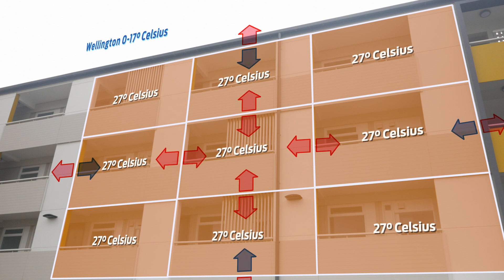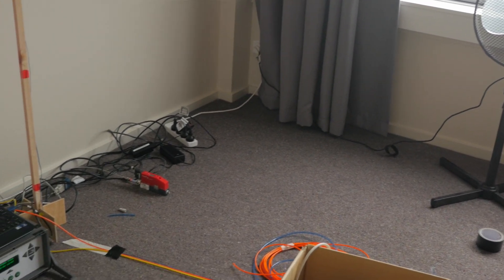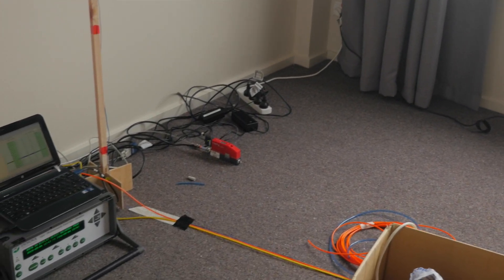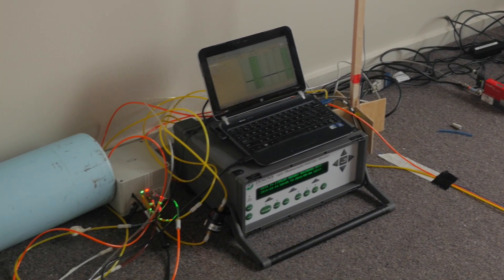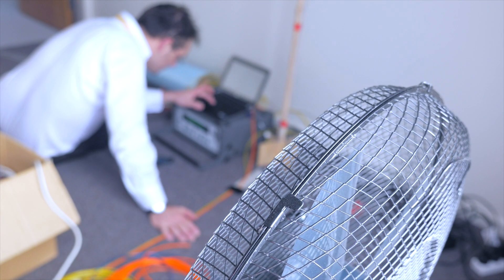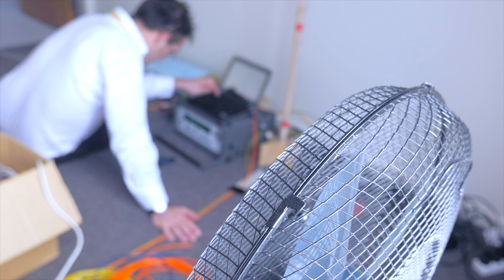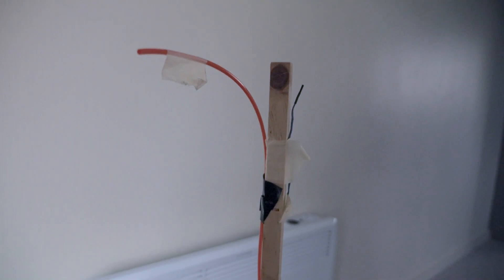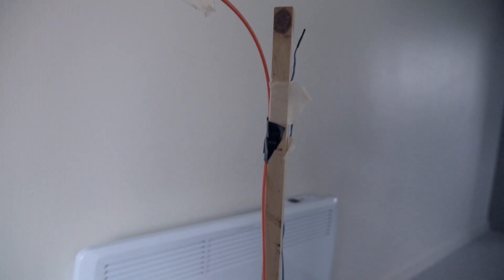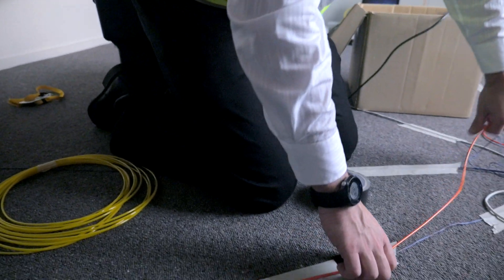We're actively using this computer system here to control the temperature inside the apartment to this set point. We've got fans that are mixing the air, making sure we're getting a consistent temperature across the apartment, and an array of thermocouples spread around the building so we can actually make sure that we are getting that consistent temperature.